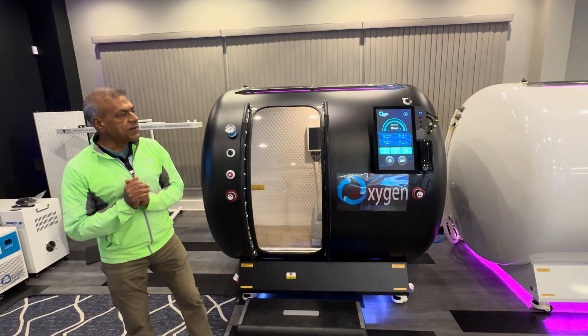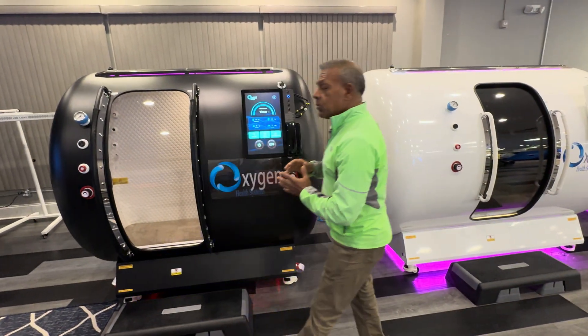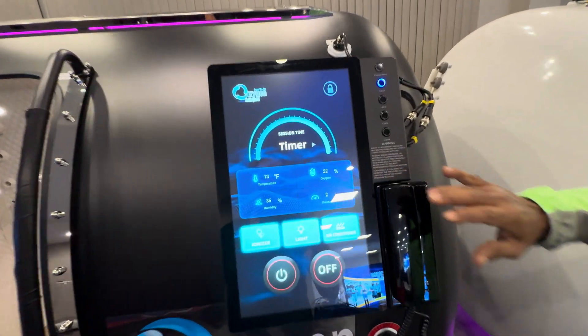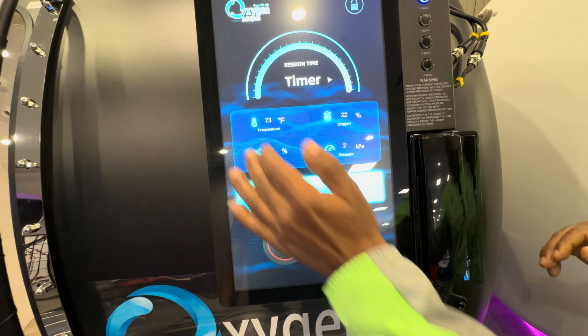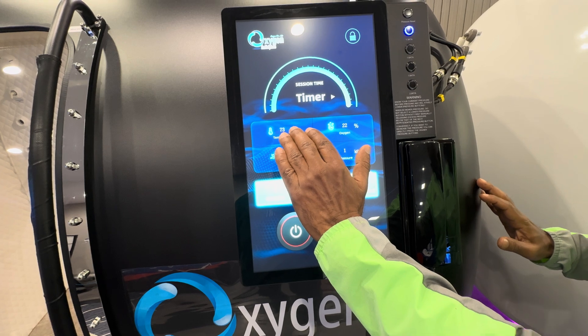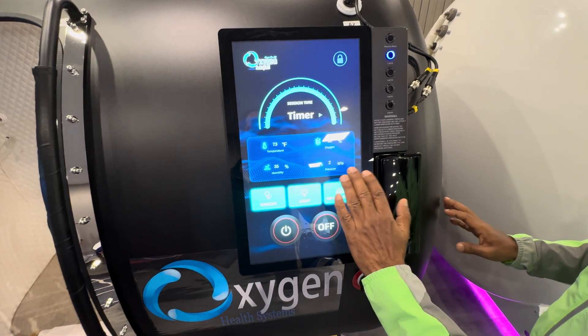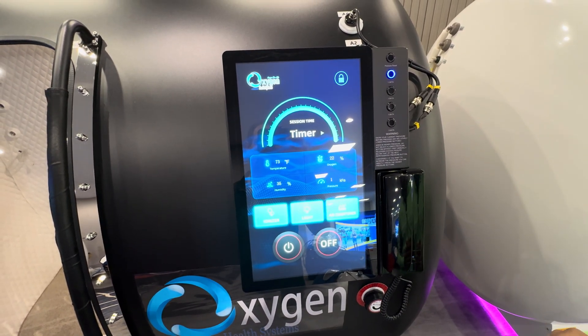Now let's take a look at some of the external features. The first thing we'd like to point out is the external control panel. It is designed with simplicity in mind — a four-quadrant layout equally divided, with the top left corner being temperature, top right corner the percentage of oxygen, followed by pressure and relative humidity.